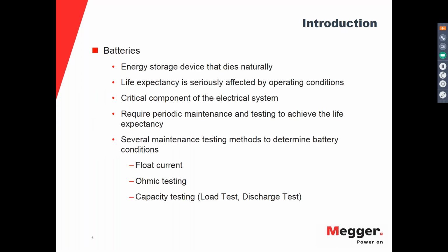So to start, batteries are a critical component of the electrical system, but they are a device that dies naturally. The life expectancy is determined by the manufacturing process and the type of battery that you get. Usually for vented lead acid batteries it is around 20 years. For valve regulated batteries, it's around 10, 15 years or even lower than 10 years. And all of this expectancy is seriously affected by the operating conditions. Just having a charger not set correctly is going to affect the life of the battery.